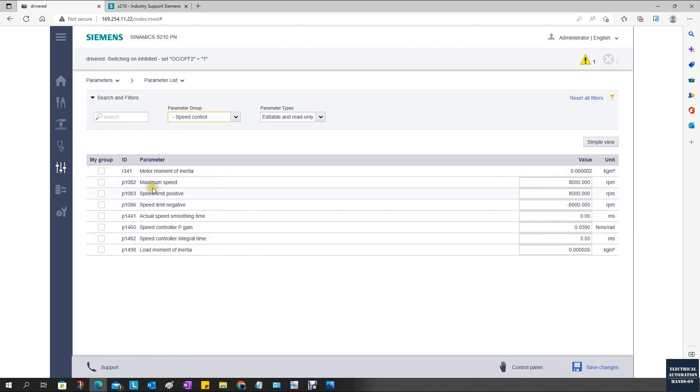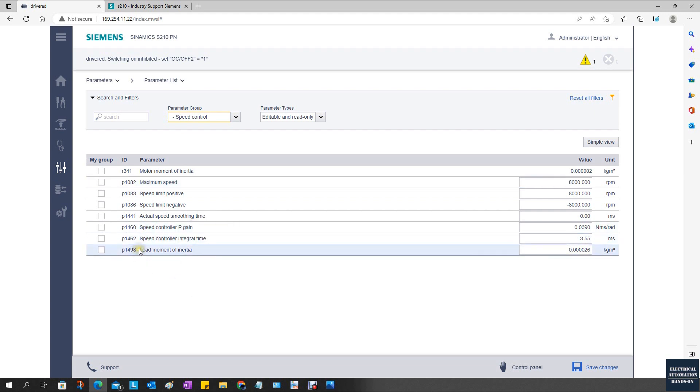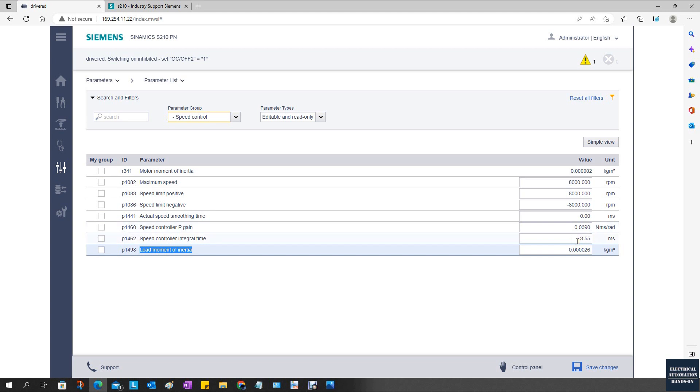We will see the maximum speed, the speed controller P-gain, this integral time, and also this load moment of inertia value. You can manually change those parameters. Based on the tuning parameter, you can first gain some experience from this P-gain and the integral. Then, according to your real performance, based on the learned parameter, do further fine tuning. This is the speed gain.